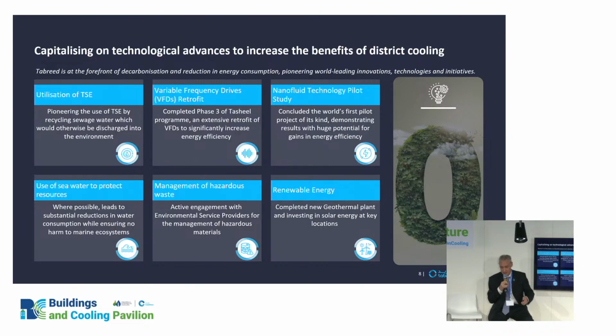So in our projects in Dubai now, rather than using very expensive desalinated drinking water for our cooling towers, we take treated sewage effluent from the municipal sewage system. We do some extra treatment - we've developed in-house water treatment capabilities - and we use that water to run through the cooling towers to provide the first stage of cooling for district cooling. That's a great use of wastewater, and then we put it back into the wastewater network once we've finished with it.